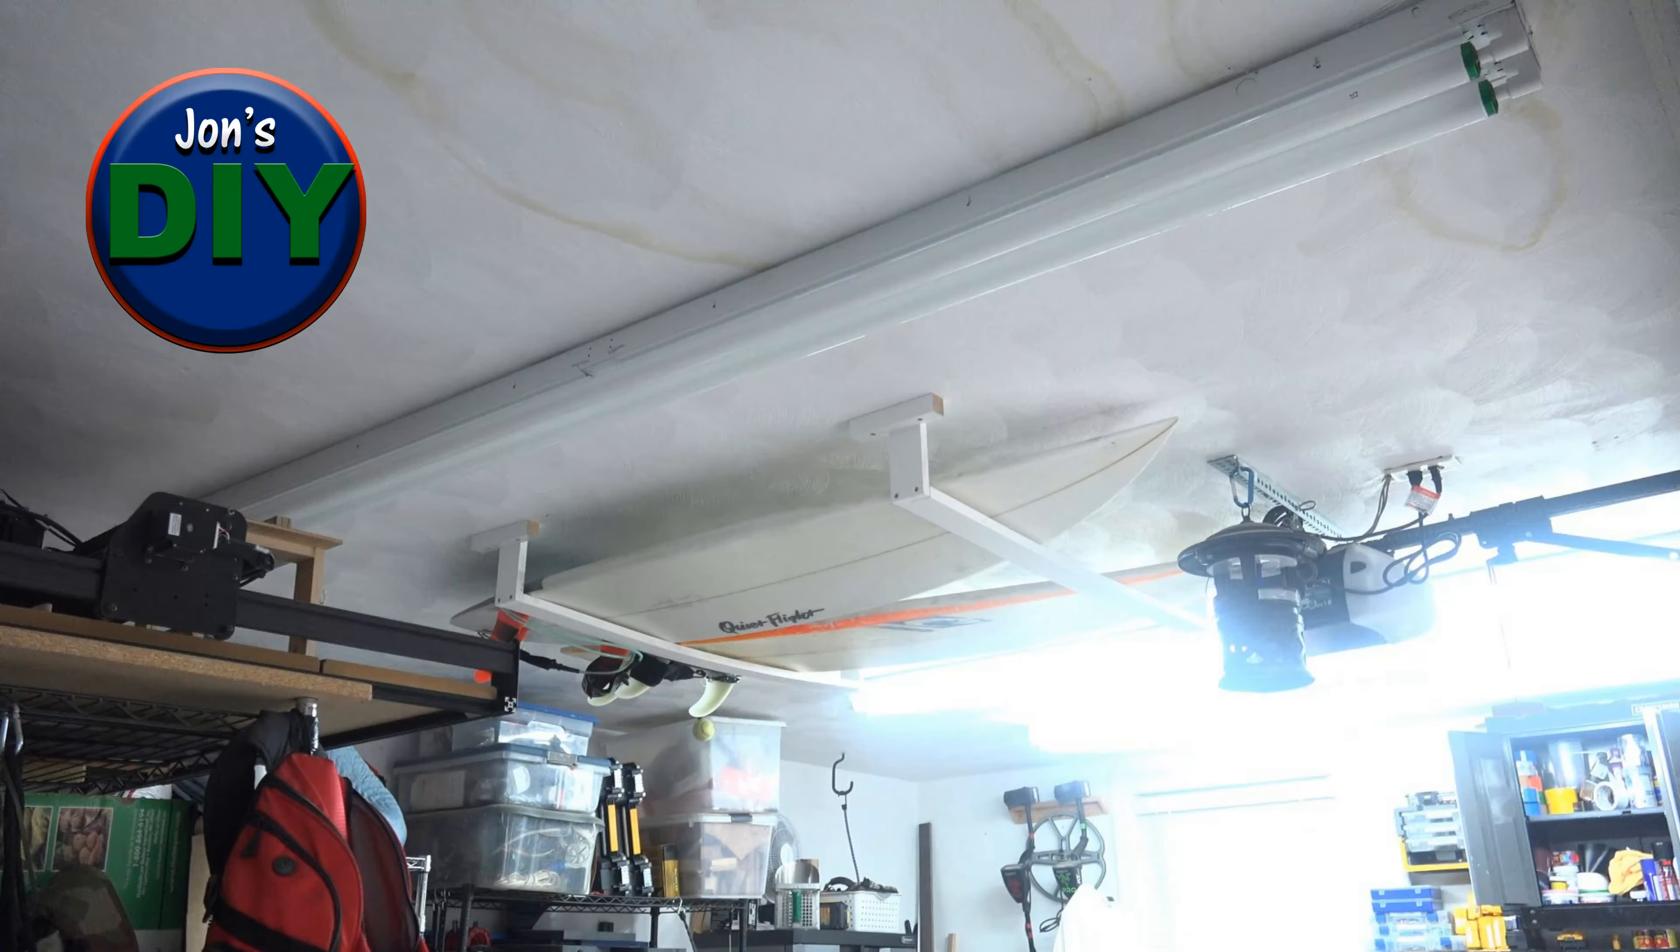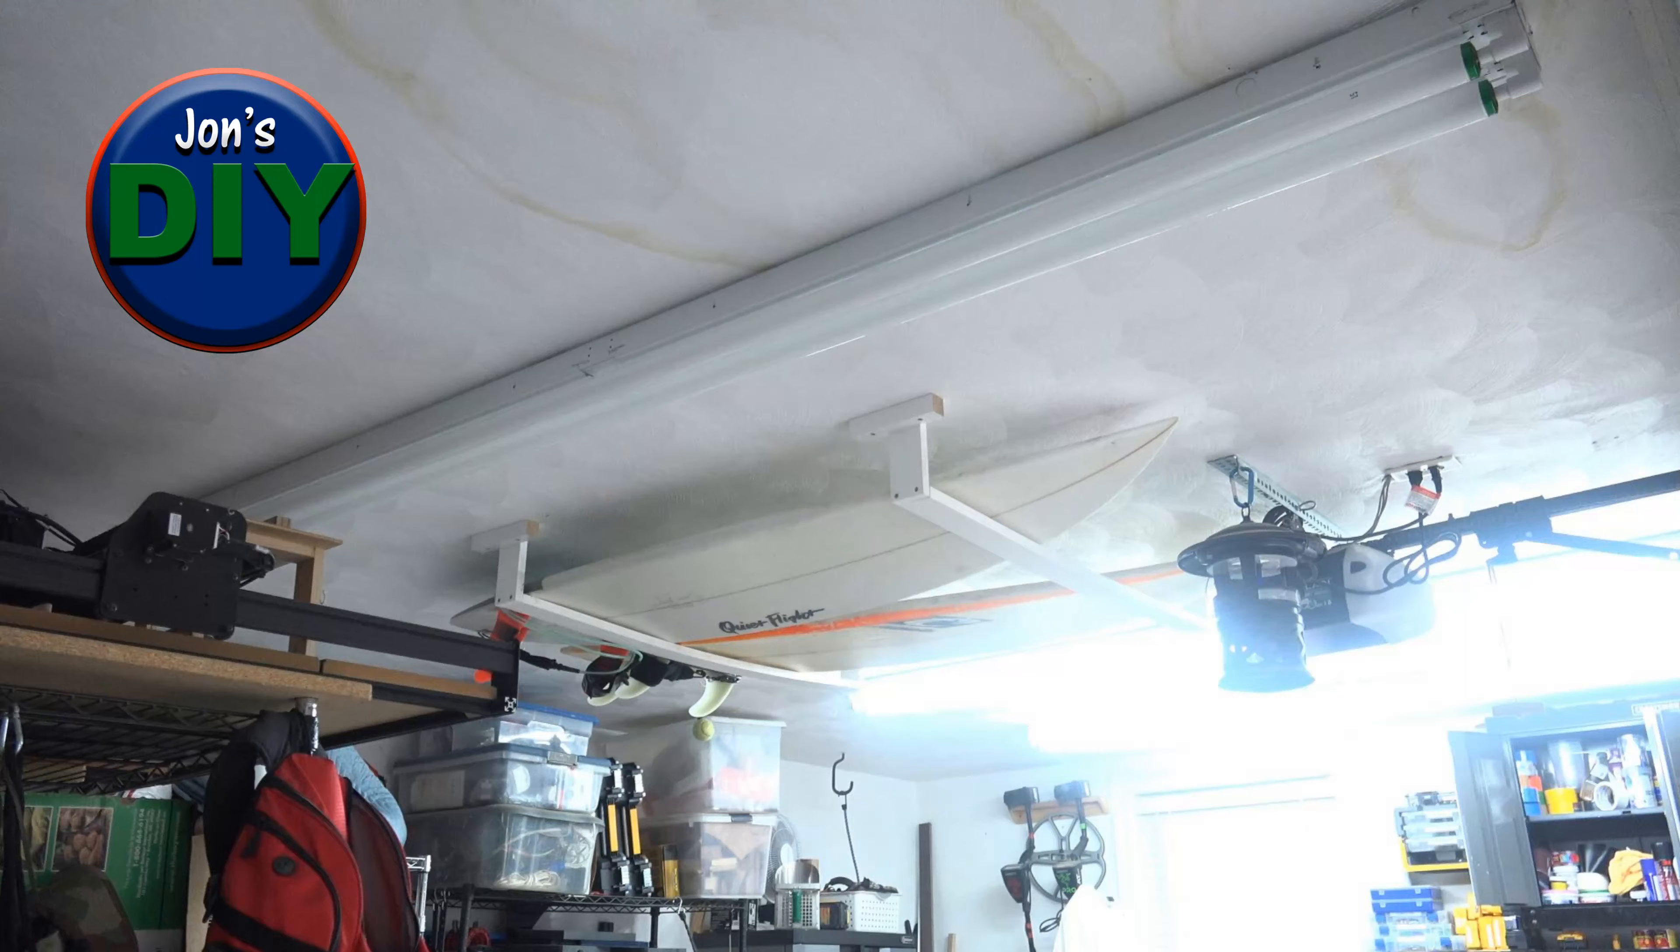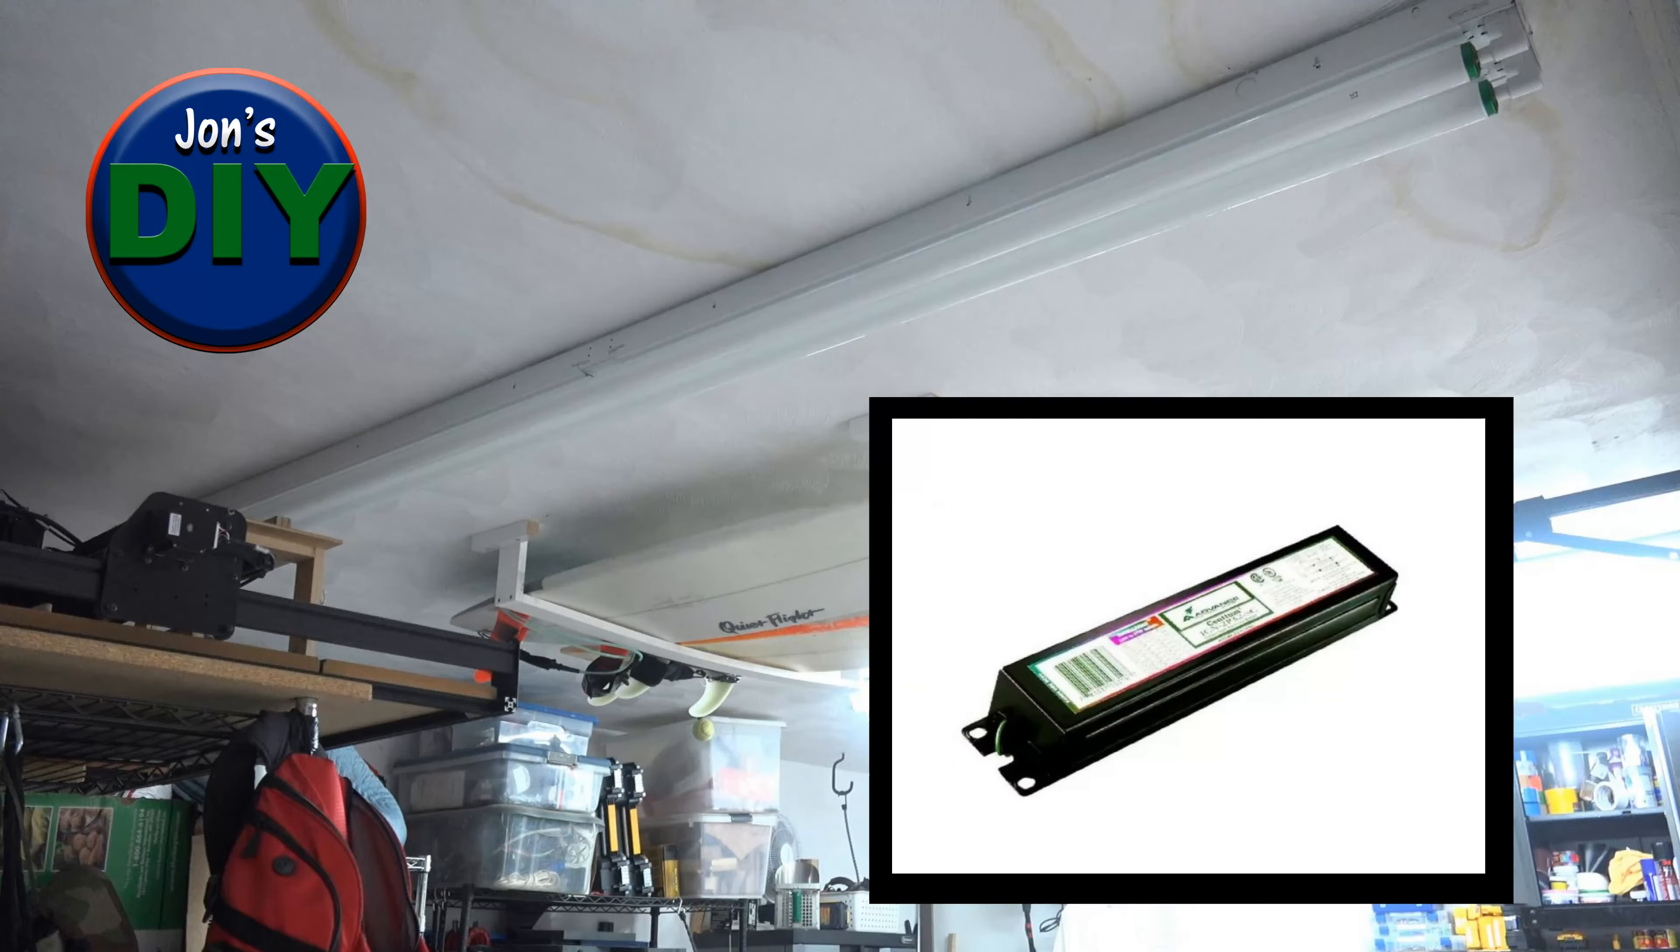So your fluorescent lights went out and the first thing you do is swap them out with a known working pair. If they still don't work, the issue is with your ballast. Well, if you're in my shoes, then your ballast was probably old and was a magnetic ballast.